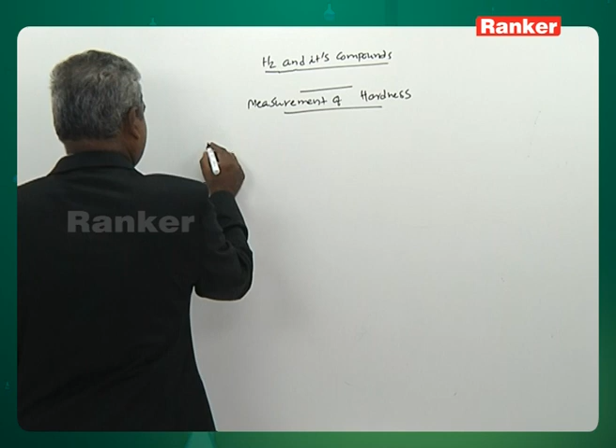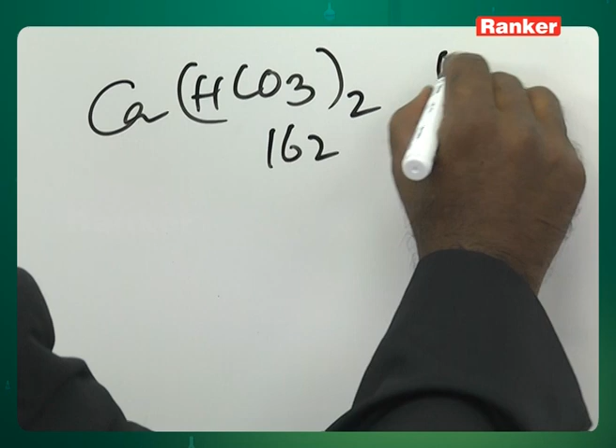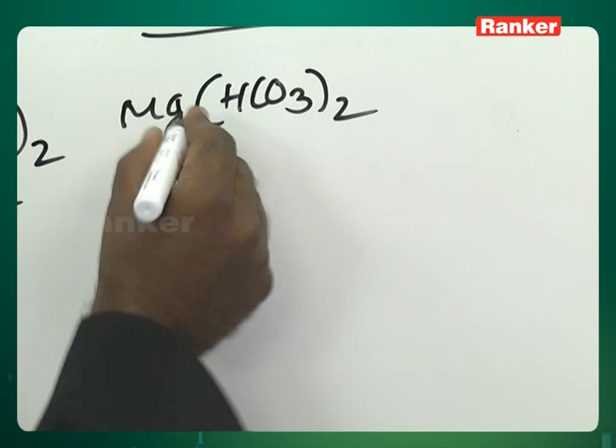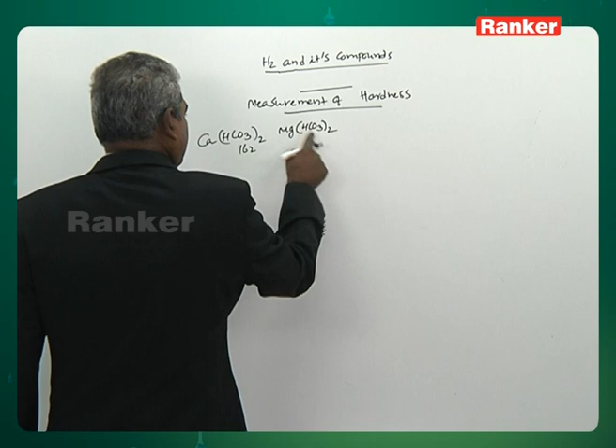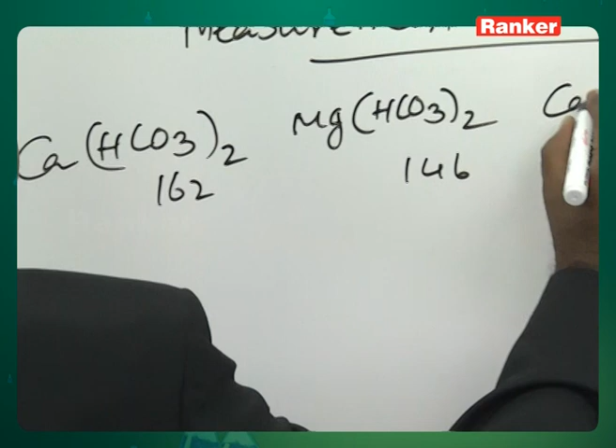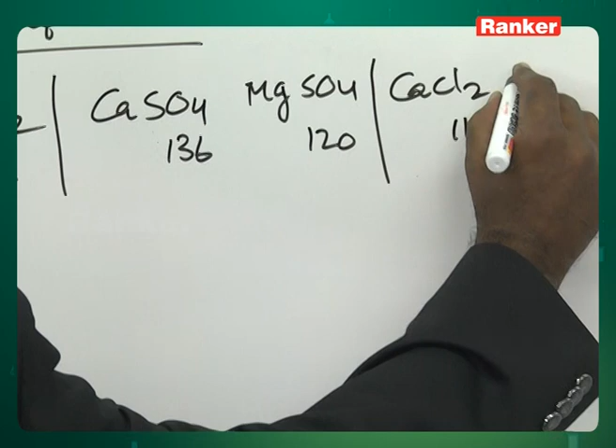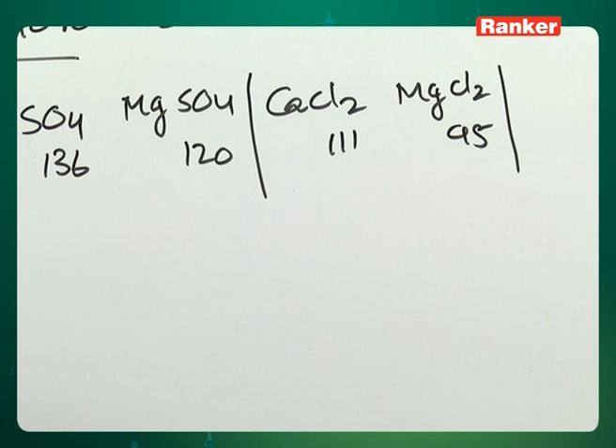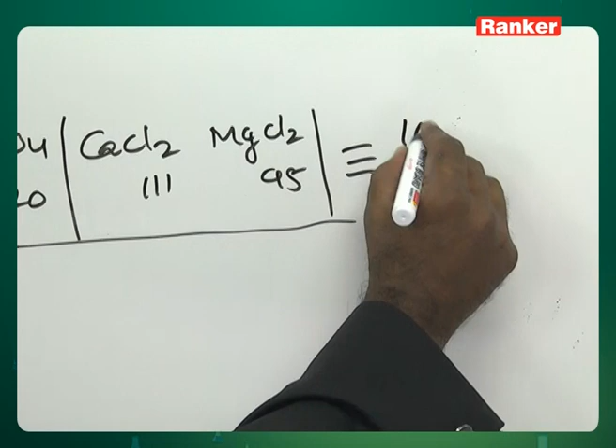Now, first of all, let us look at the molecular weights of the 6 salts. Calcium bicarbonate is 162. The corresponding magnesium salt will be 16 less than that, since the atomic weights of calcium and magnesium are 40 and 24. So, magnesium bicarbonate will be 16 less, 146. Calcium sulfate is 136. The corresponding magnesium sulfate is 16 less, 120. Calcium chloride is 111, and the corresponding magnesium chloride is 95. So any of these is equivalent to 100 when it comes to calcium carbonate.